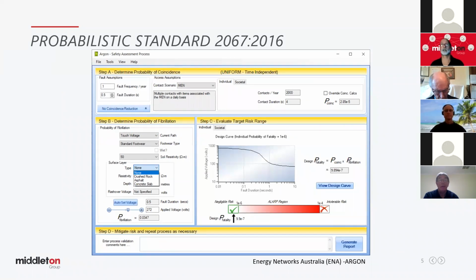What contact scenario? This is an image, so we won't see the others, but there's 4 contact scenarios. Is it on the MEN of your house? Is it in your backyard? Is it an urban situation like a conductive pole in the street, or is it indeed remote, out, like our 500 kVs or structures out in the paddocks? Because obviously with the different scenarios, there's different numbers of contacts per year and different durations per contact, as you can see on the right-hand side.